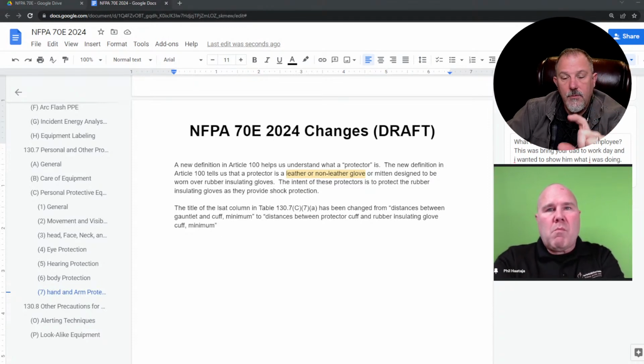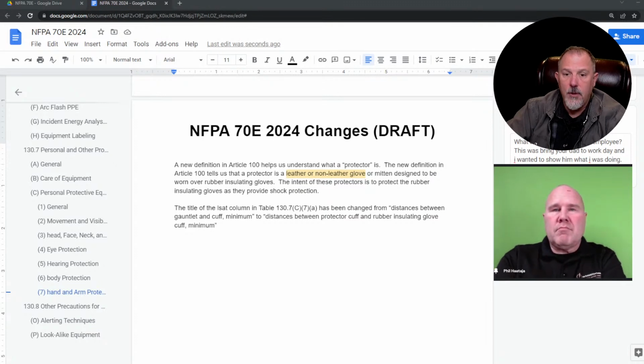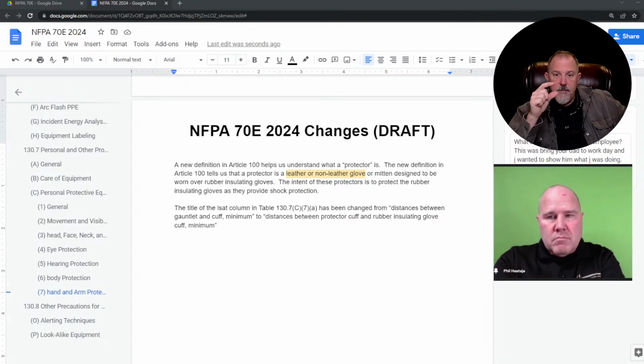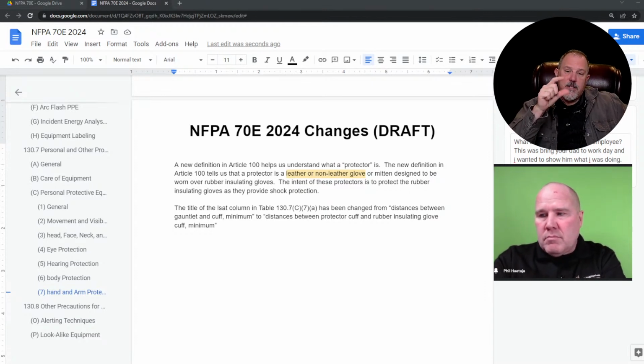And they give you different inches based upon 00, 0, and 1 through 4. A 4 is 4 inches, 3 is 3 inches, 2 is 2 inches, 1 is 1 inch, a 0 is 0.5 inches, and the 00 is also 0.5 inches. So the smallest amount of rubber insulating glove sticking out of the leather protector is 1/2 inch, and the most is 4 inches.